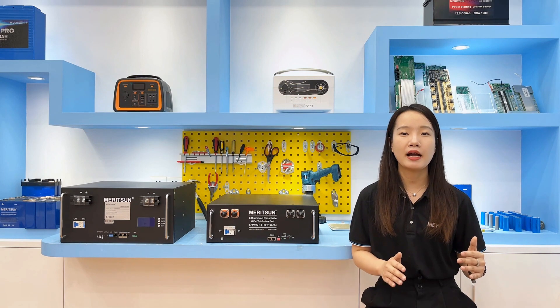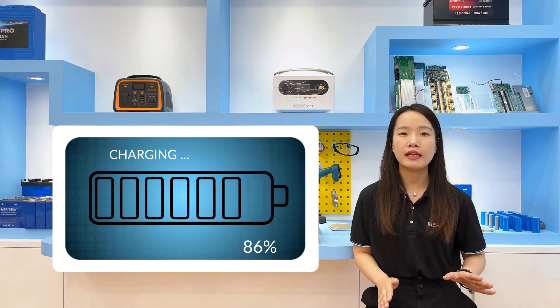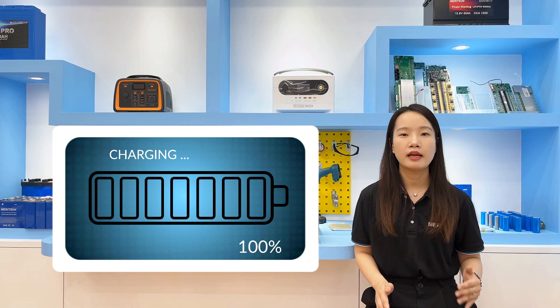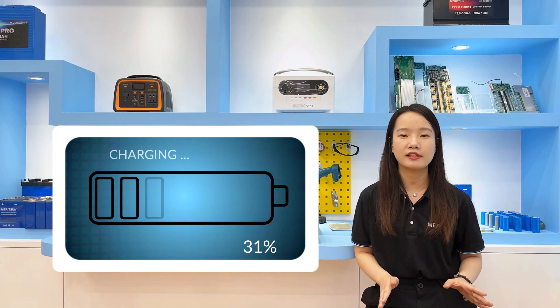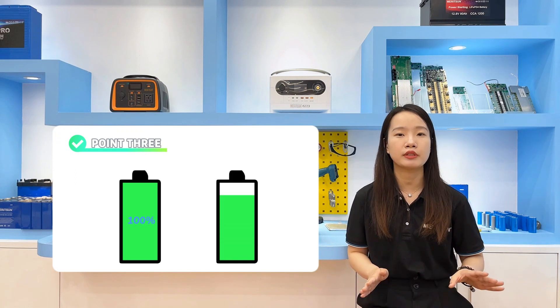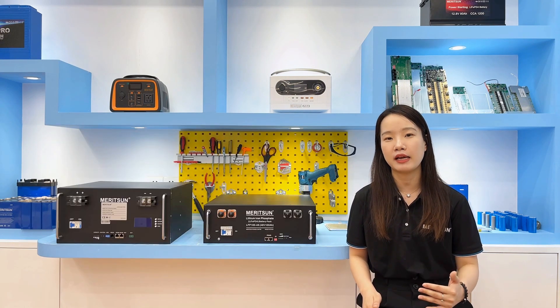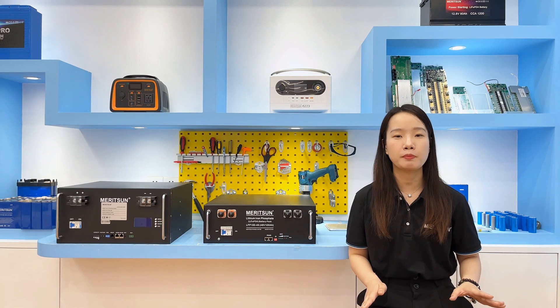When fully charged, the resulting high current increases stress on the electrode — with stress thickening and expanding cells to allow all ions to penetrate. When the battery is fully discharged to 2.7V per cell, a chemical reaction occurs inside, making the electrolyte oxidization change and the battery age faster. Since lithium batteries have no memory effect, even charging to only 95% SoC instead of 100% has no negative effect but can prolong battery life. You can also reduce the depth of discharge by expanding the battery capacity of your system.